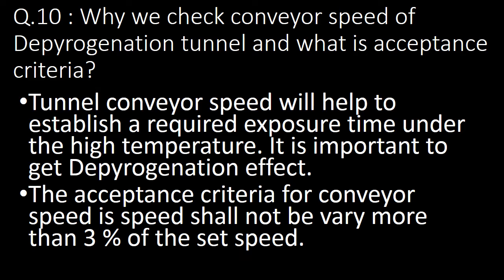Next question: why do we check conveyor speed of the depyrogenation tunnel and what is the acceptance criteria? Tunnel conveyor speed helps to establish a required exposure time under the high temperature, which is important to get the depyrogenation effect. The acceptance criteria for conveyor speed is that speed shall not vary more than 3% of the set speed.